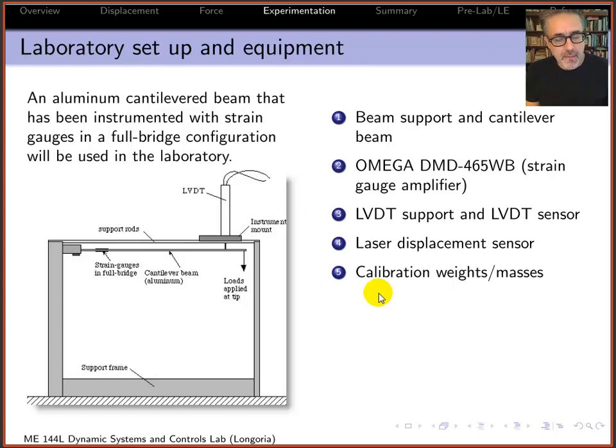And after you've taken all your data, you want all that displayed on the screen. You want to be able to look at it and make sure that you're done. And then you want to be able to tell it, okay, model that, give me the calibration, or save that, and also save that data if you like. You can add the save part. I haven't added it on this one.